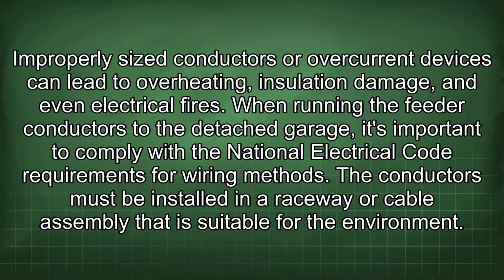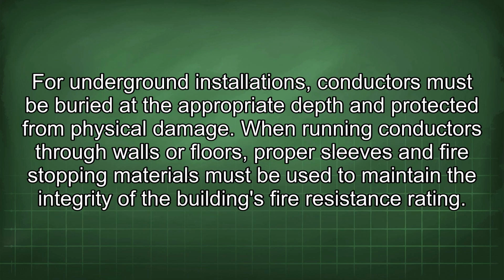When running the feeder conductors to the detached garage, it's important to comply with the National Electrical Code requirements for wiring methods. The conductors must be installed in a raceway or cable assembly that is suitable for the environment. For underground installations, conductors must be buried at the appropriate depth and protected from physical damage. When running conductors through walls or floors, proper sleeves and fire-stopping materials must be used to maintain the integrity of the building's fire resistance rating.